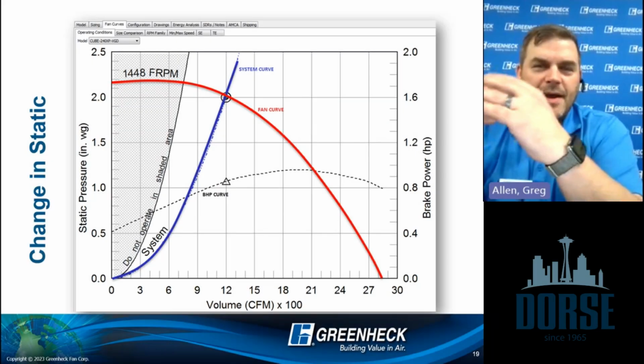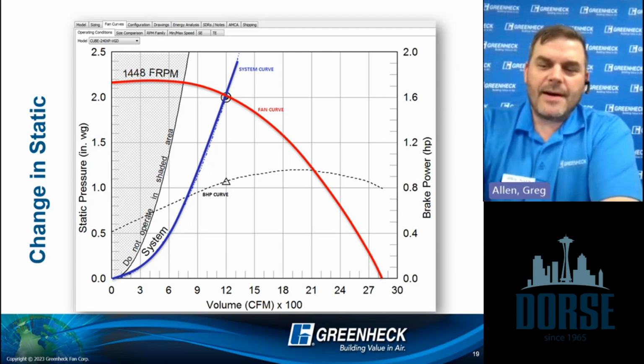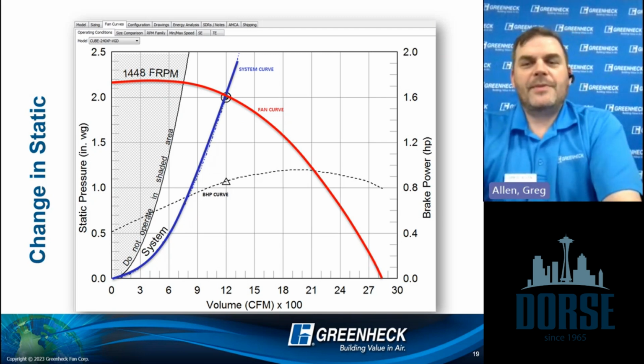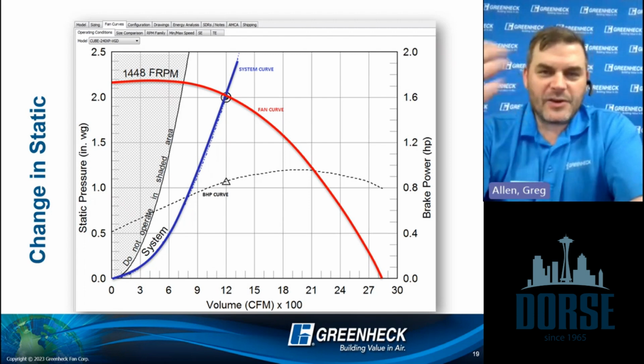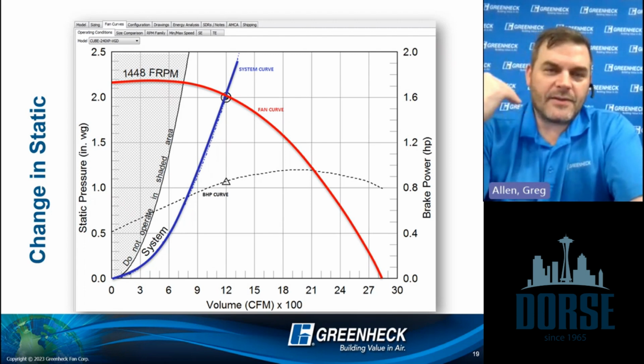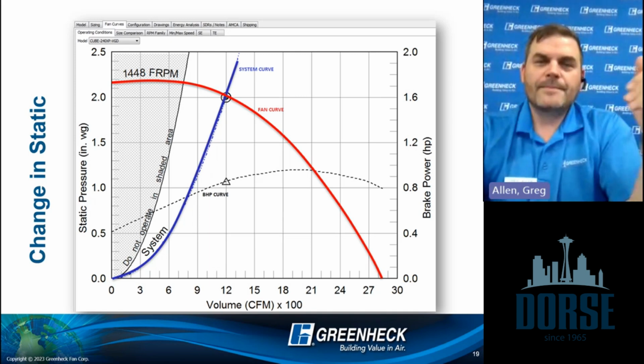On the screen, I've got my fan curve, my system resistance curve, right? I've got my interaction. So my question to you is, what happens when you've added up all the ductwork? I needed 1200 CFM against 2 inches. That 2 inches represents all those elbows, the whole works.